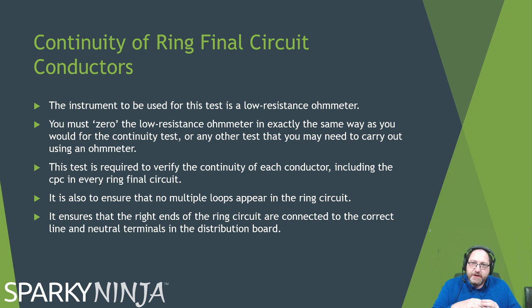Continuity of ring final circuits. Remember, I'm pushing fast through this. This is in no way how quick you should be learning it on a course. It should be a lot slower. Time to digest all this and have a go at it. With the ring final though, we're still going to use the low resistance ohmmeter. It will have to be zeroed. The difference here is we've got to make sure that there are no internal loops and that the ring is in itself a ring. If the ring isn't a ring, then we're going to have potential overload because we've got a 2.5mm cable on a 32 amp breaker. That's no good.